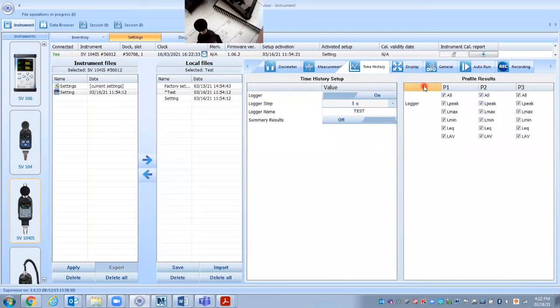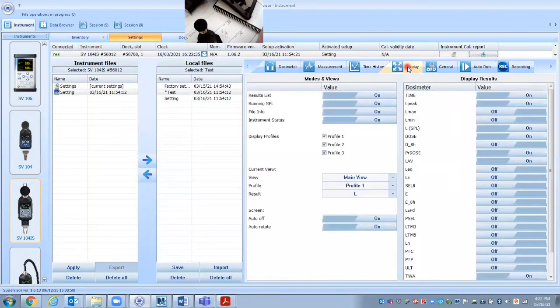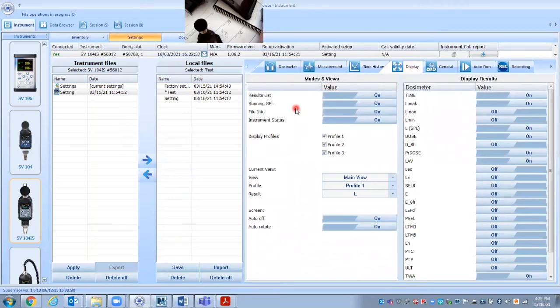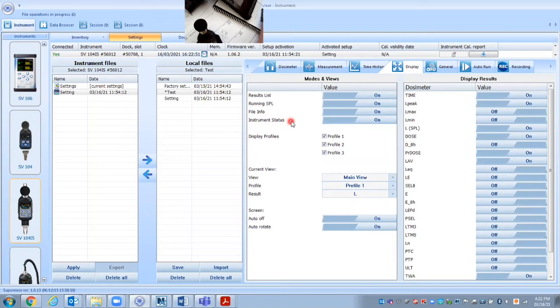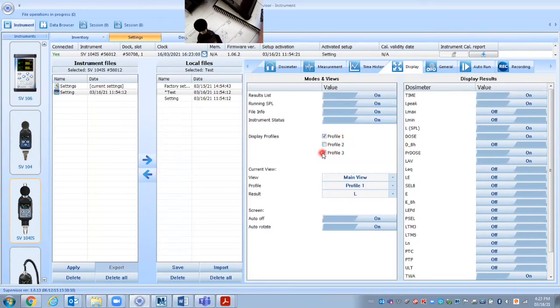Let's look at the options under the display tab. I click on this. Now, these are things basically the way that or what you will see on the dosimeter. So we've already set what it's going to be recording. But we can have and most of the time you would turn this on like you'd want to have the file information, the instrument status, like the battery and things like that. If we're only using profile one for ACGIH, we could turn off these other profiles because we're not really using any of those.